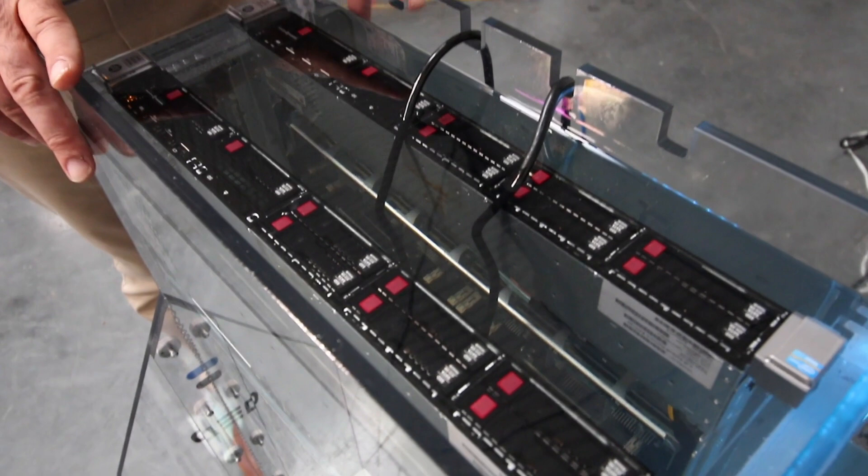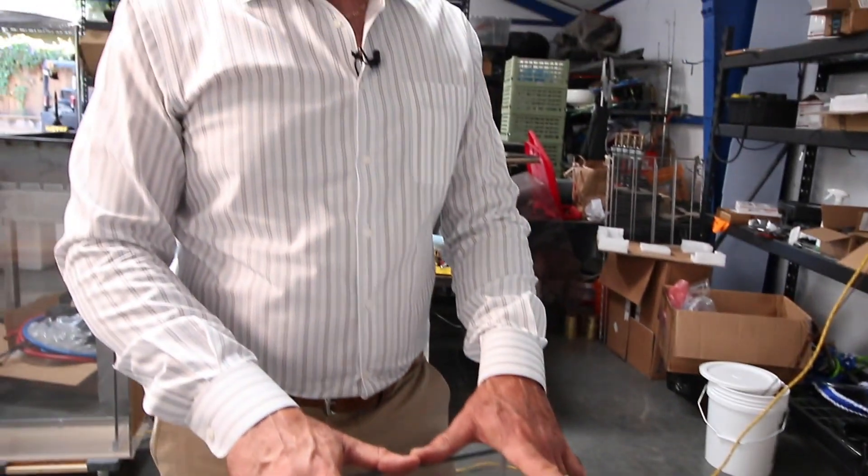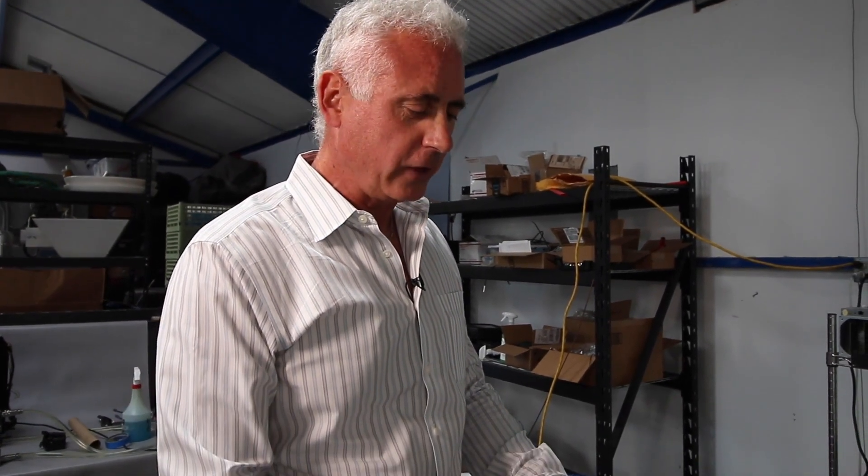Before you immerse any device, you really need to focus on three things. One is the fans and the removal of the fans in order to save power. If you leave the fans on these devices, a lot of people think that they actually will circulate the fluid. The fluid in fact doesn't need any assistance in circulation from the fans. The fans are designed for use in air, so they're not very efficient for moving fluid around.